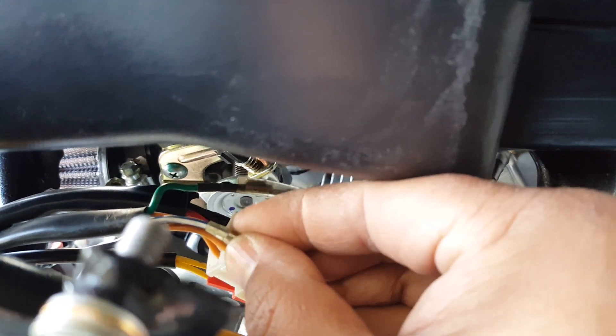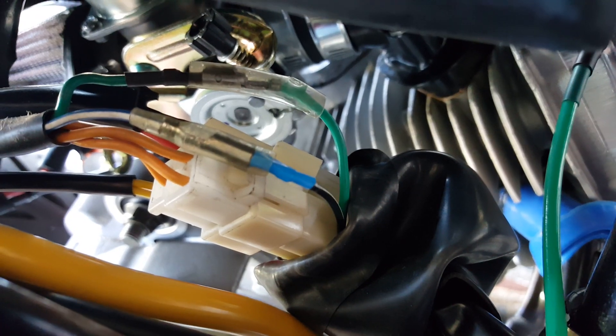Maybe pull a little bit more. Heat shrink protects the insulation. And I think we already put some dielectric grease — you can see here a little splattering of grease marks. There we go. So then we got our gauge connector here — we're going to go and silicone that tip as well once we secure this one. I'm going to silicone and secure everything once everything is fixed. The reason why is you don't want to put silicone and start moving pieces around — then it's not going to really concave the joints. You can see here I did a great job putting the silicone here as well. That silicone there helps to hold that wire. That tape was just a little bit of reinforcement that I can remove afterwards. I use a lot of silicone in certain areas of plastic to secure it. But yeah, it looks a little dark and weird looking, but for the most part at least we can see our wire joints and it's kind of sealed in there.